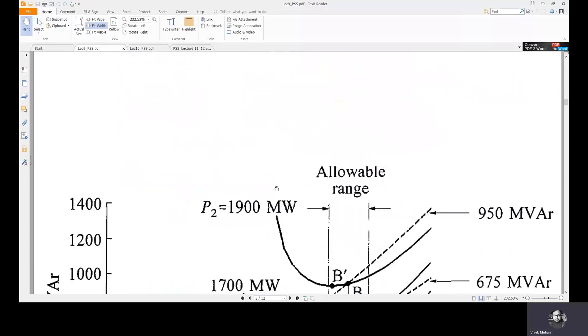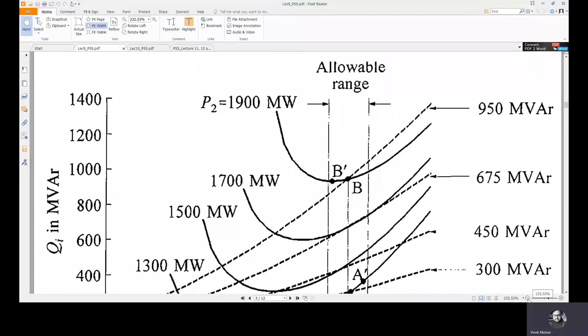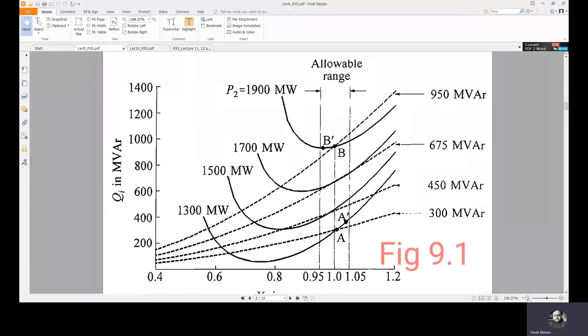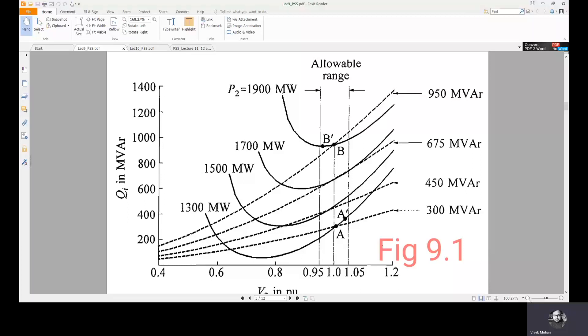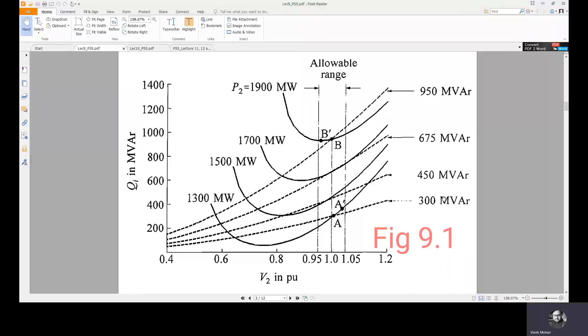In this analysis, the QV curve is drawn where the vertical axis represents the injected reactive power in MVAR and the horizontal axis represents the receiving end voltage V2 in per unit. We have different curves for different loading levels: 1300, 1500, 1700, and 1900 megawatts. The dotted characteristic shows the capacitor or reactive power compensation device, and the solid characteristic shows the QV characteristic of the system.